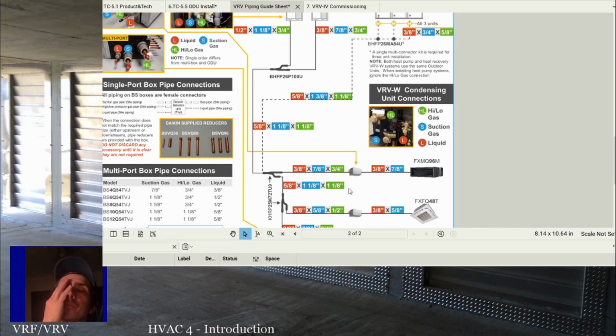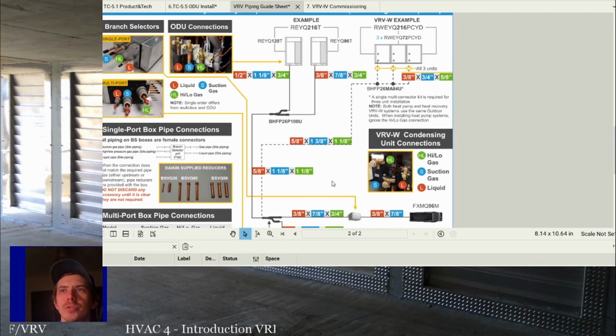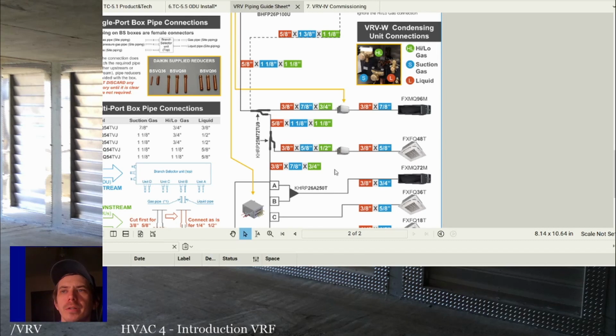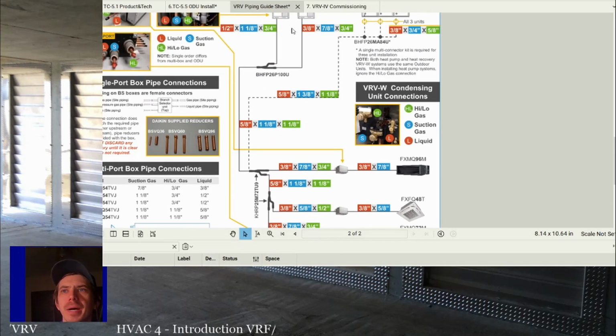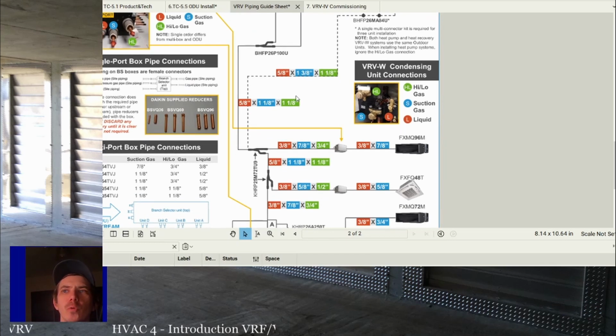So basically, when the VRF system communicates between indoor and outdoor unit, or from branch selector to branch selector, all that communication is going back to the outdoor unit. Basically, how it tells which unit it's talking to, because this wire just goes from here to here, then from here to here, the only way the outdoor unit knows it's talking to this box, at its most basic form, is because it takes longer to get there. It's a longer resistance from here to there instead of from here to there. So because it knows this box is first and this box is second in the wire run, it knows which box it's communicating with based on how long it takes to get there and back. That might not be exactly how it works, but it's an easy way to think about it.